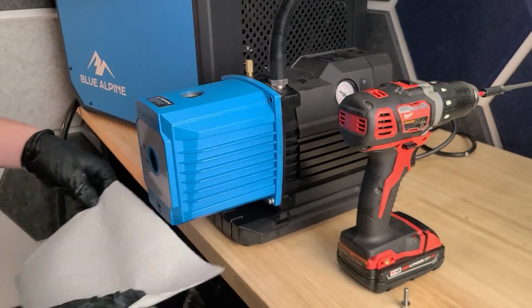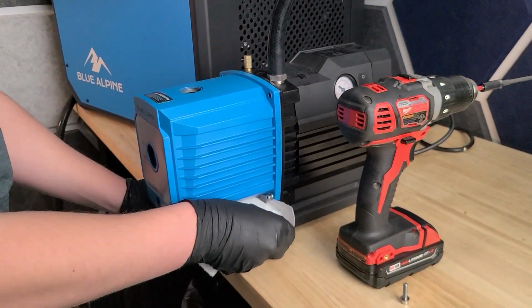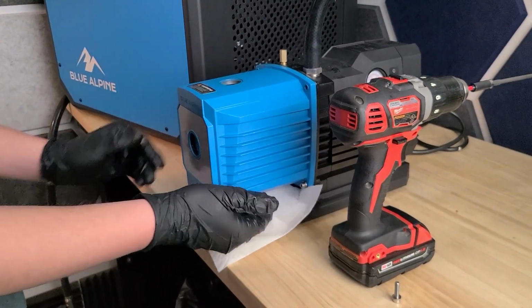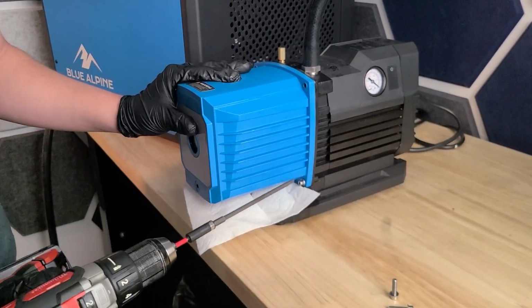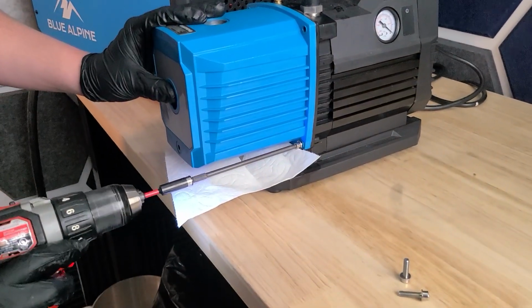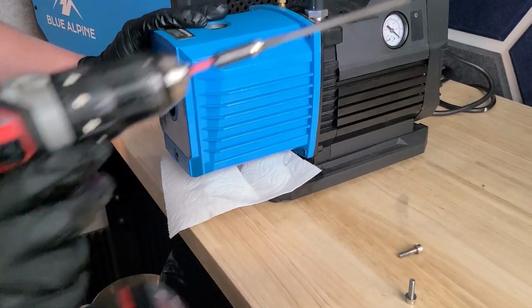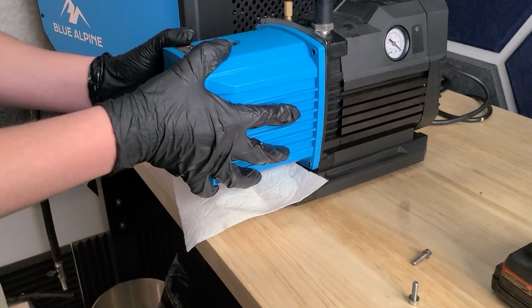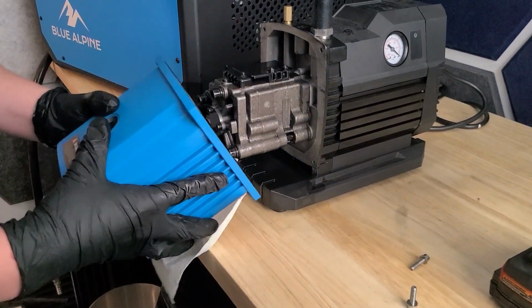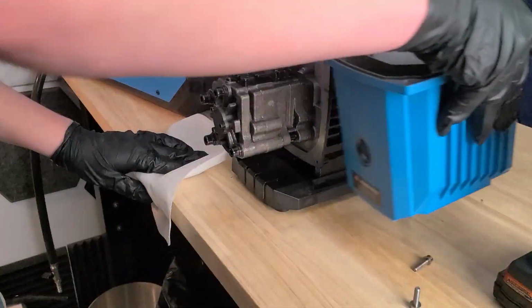What I like to do is add a paper towel underneath your vacuum pump when taking the head off, so if there is any oil still sitting at the bottom of your vacuum pump, it will fall on the paper towel and not make a mess. And taking the last screw out, hold the vacuum pump, and the first thing you're going to want to do is tip it back so the oil stays in the chamber. And then you're going to want to take your head and set it to the side.